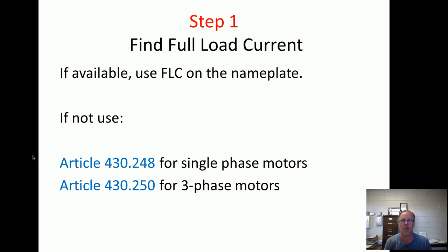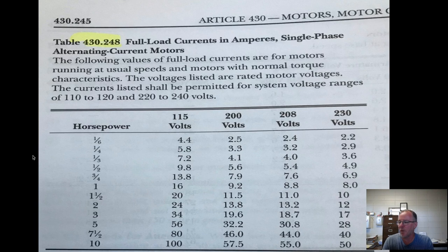Step one is so important. First of all, if it's available, you use the full load current on the nameplate. But if it's not available and you know the horsepower and the voltage, then you go to Article 430-248 or 430-250, depending on whether the motor is single-phase or three-phase. So right here is full load current and amperage for single-phase AC motors, Table 430-248.